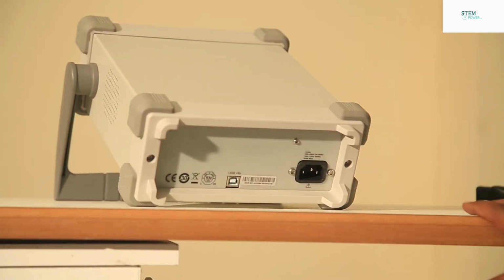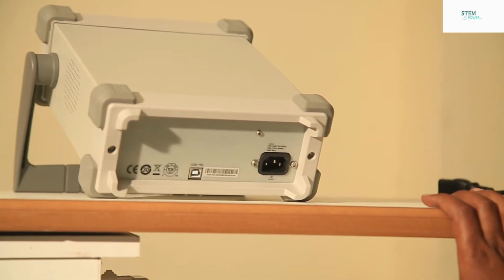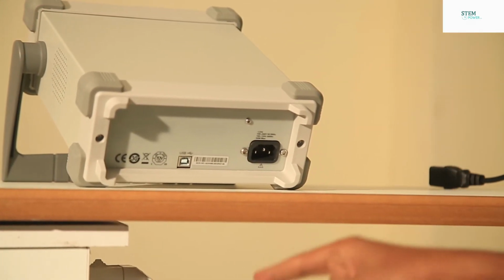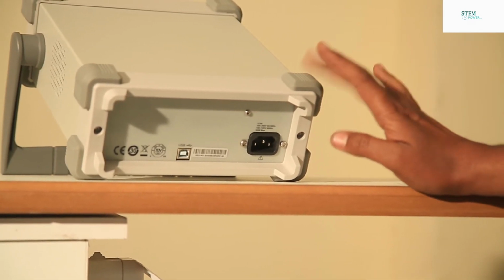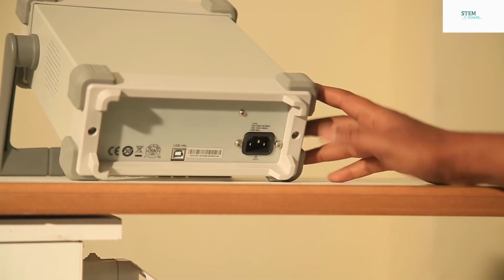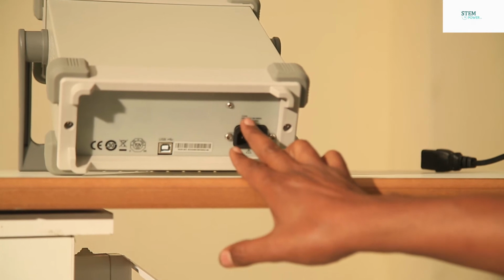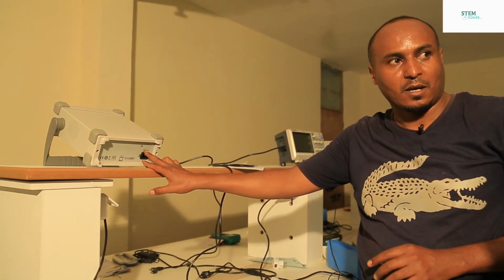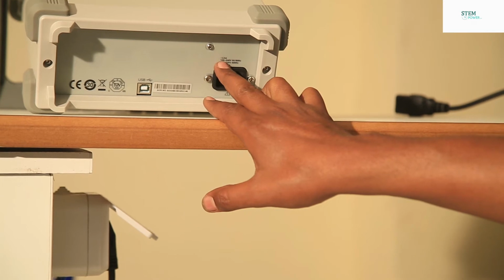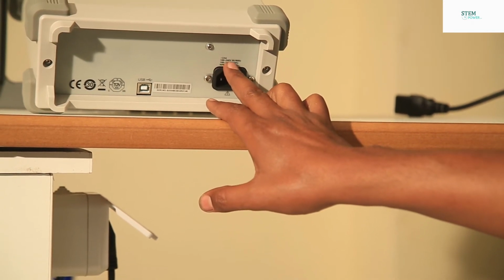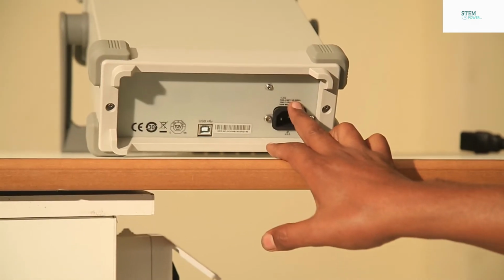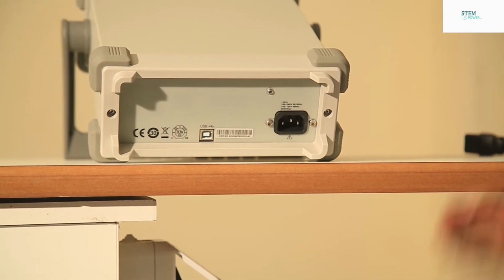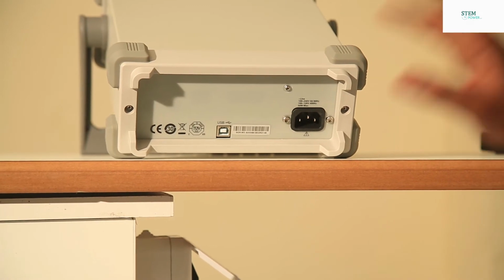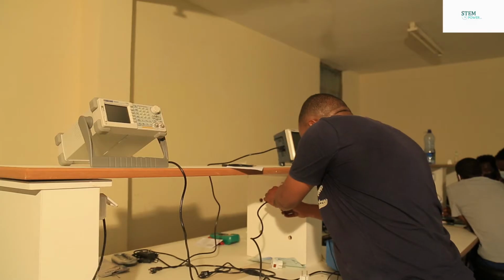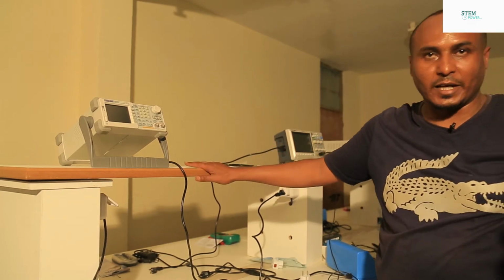For any electrical equipment, the first check is a power inspection, because you have to check the line voltage you are going to use on your workbench, and it should be compatible with the machine's required voltage. So we check the power supply: the line voltage should be around 110 to 220 volts at 50 or 60 Hz. In our country, the line is 220V and 50 Hz, so it is compatible. Connect or plug into the workbench socket outlets.